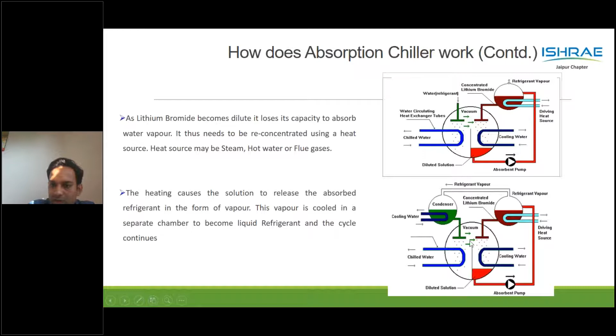You can see from a heat source, we are able to produce chilled water. From hot water to chilled water, how it is produced, there is no consumption of electricity here. There are a few pumps like the absorbent pump, vacuum pump, and evaporator pump, which consume minuscule electrical power. The rest of the vapor absorption machine runs on heat.